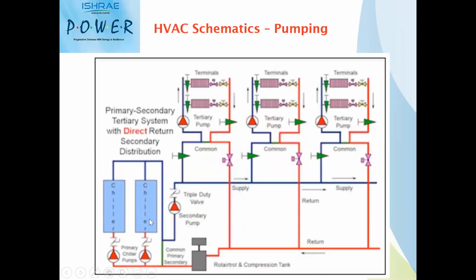We have typical tertiary pump systems as well, where we have primary, secondary, and maybe tertiary systems, for particular applications where you have bigger loops and bigger distribution side areas, where you want to have tertiary systems also. The pumps are designed to cater to a particular area. So the primary pump will circulate the water from the chiller to the secondary pump. Secondary will have a distribution header from where again tappings are taken, and particularly for that particular zone, tertiary pumps are used.